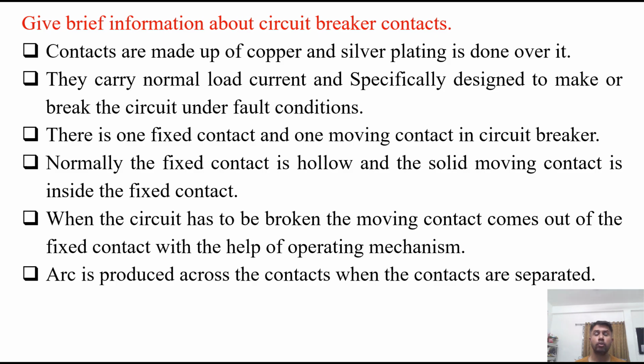Give brief information about circuit breaker contacts. So, contacts are made up of copper and silver plating is done over it. They carry normal load current during normal healthy condition and are specifically designed to make or break the circuit under fault conditions. There is one fixed contact and one moving contact in a circuit breaker. Normally, the fixed contact is hollow type and the solid contact is fixed inside the fixed contact like this. So, when the circuit has to be broken, the moving contact comes out of the fixed contact with the help of the operating mechanism. Arc is produced across the contacts when the contacts are being separated. So, this is brief information about the circuit breaker contacts and their function.